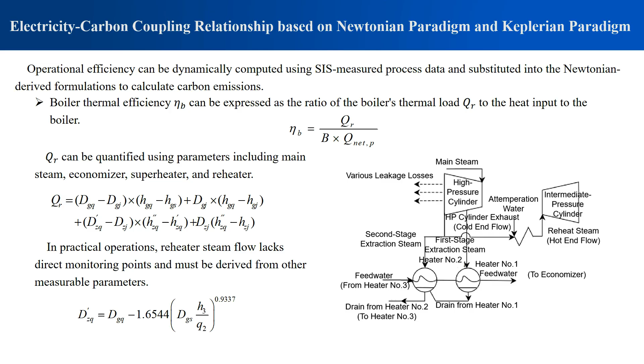Pipeline efficiency eta P equals steam turbine heat consumption QSR divided by boiler thermal load QR. QSR is calculated from main steam, superheater, and reheater parameters, again using measured or inferred process variables. Turbine internal efficiency eta I equals 3600 times internal power PI divided by QSR. The factor 3600 keeps the power and heat units consistent.